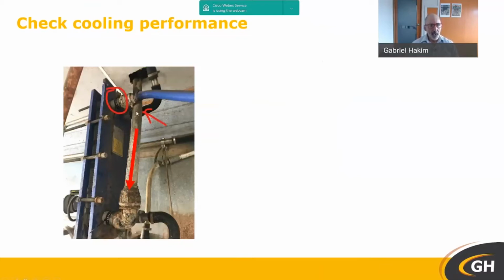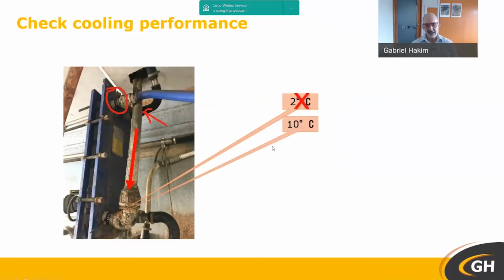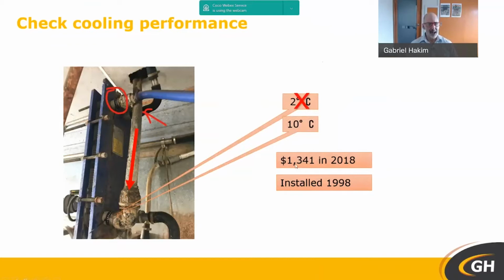Here's a prime example. We put some stickers on this plate cooler on this dairy in Western Victoria. The expectation was a 2-degree difference between milk coming out and water going in, but it was actually 10 degrees. By improving that, we could reduce the bill by nearly $1,350, and that was back in 2018. I asked the farmer why was this the case, and the problem was that's how it was installed back in 1998. So for 20 years, the plate cooler's been working the wrong way. So you can do the math to see the impact that's had.